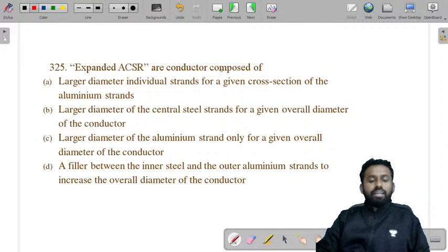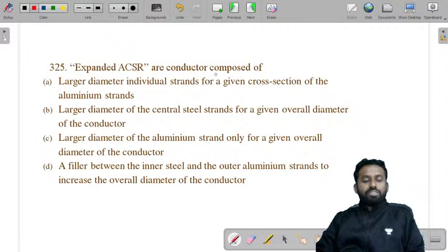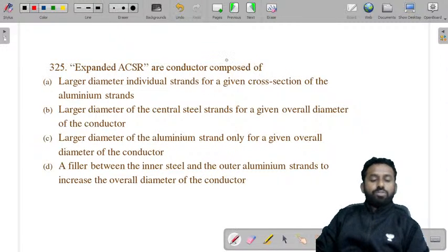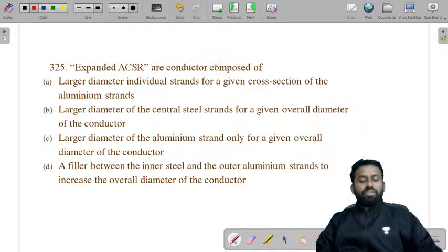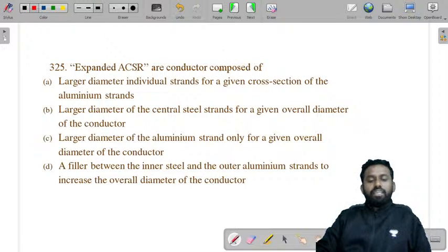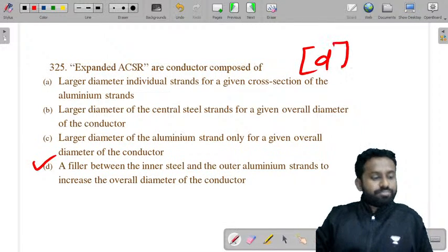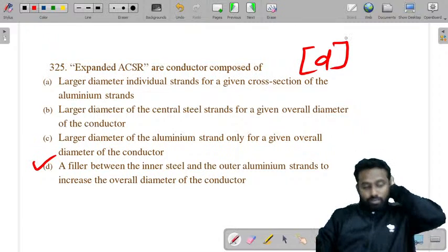So generally you can say the conductor of larger diameter increases the effective diameter of the conductor so as to reduce corona loss. So what will happen? Corona loss will reduce. Hence the radio interference level will also reduce. So a filler between the steel and the outer aluminum strands to increase overall diameter of the conductor is the correct one. So you can say the answer is D.